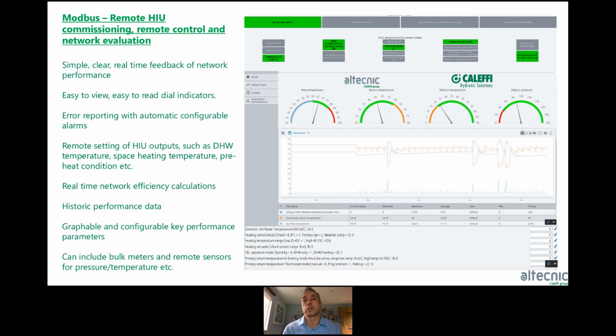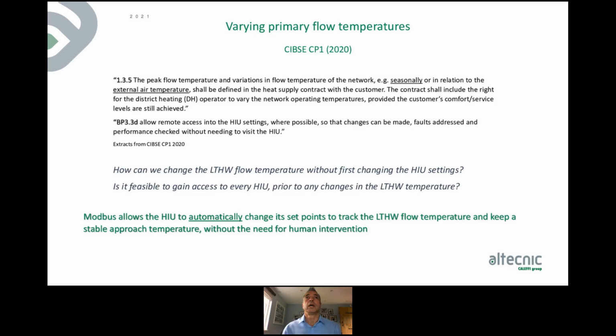You also have the ability to set parameters that can't be changed by the tenant. So you could go in and say, well, I want 50 on that HIU, and I don't want the tenant to be able to change that. And you can then set that in, and the software will make sure that that never changes from 50. So it's really flexible, gives you the option to do whatever you want to do. We can also include bulk meters from the plant room into this. We can include temperature sensors on the network, differential pressure sensors on the network, anything that has a feed from it, we can actually take into the software and display it graphically in this way. And it's very easy to tailor it to suit what you want.